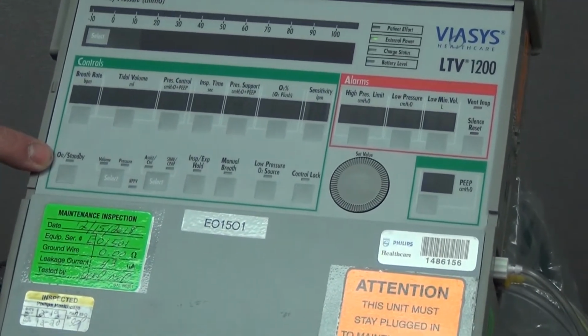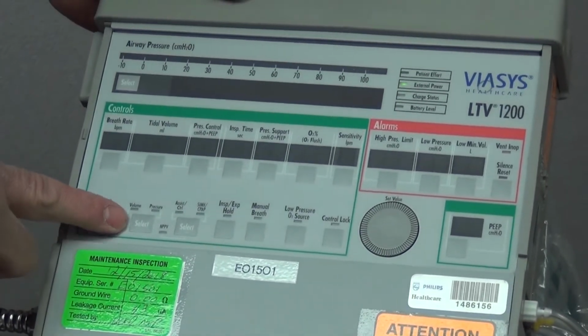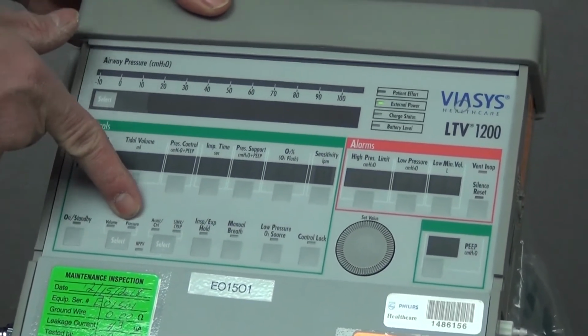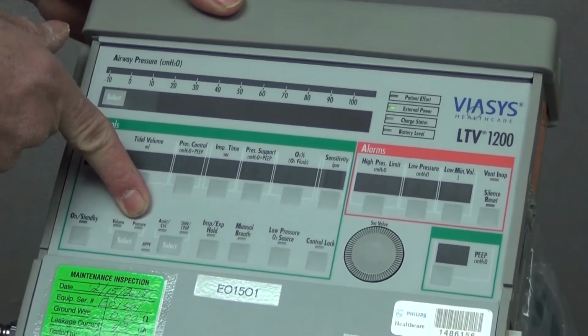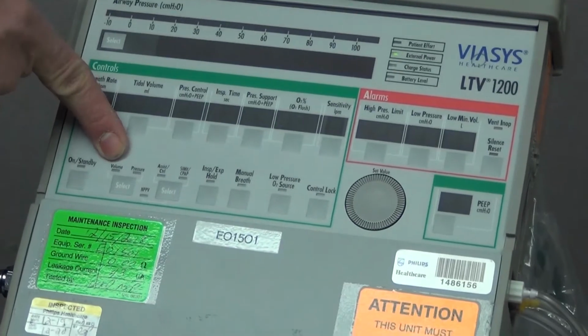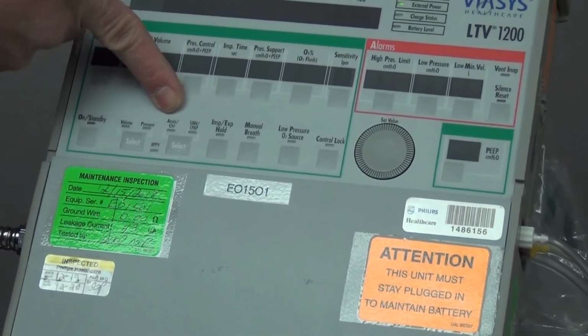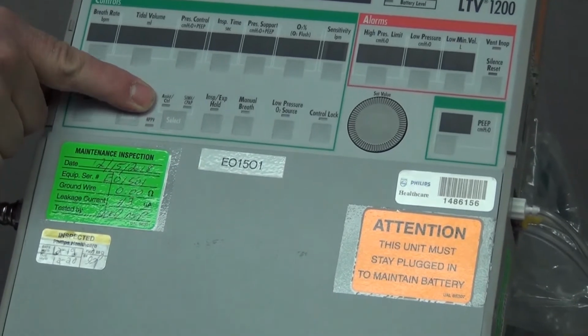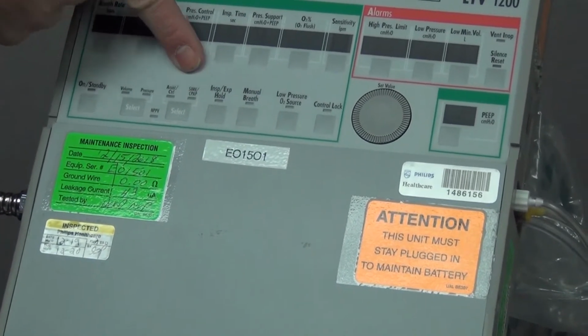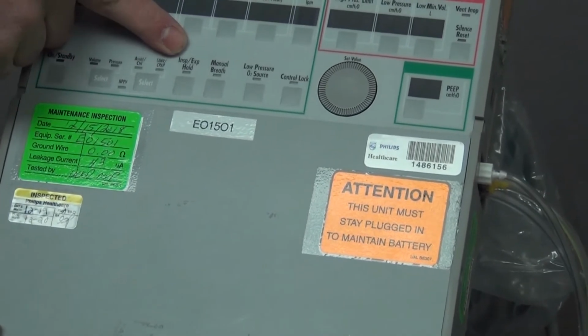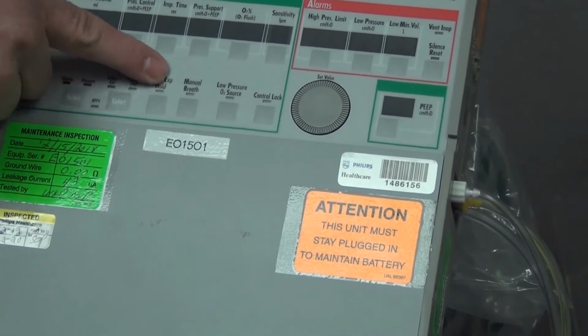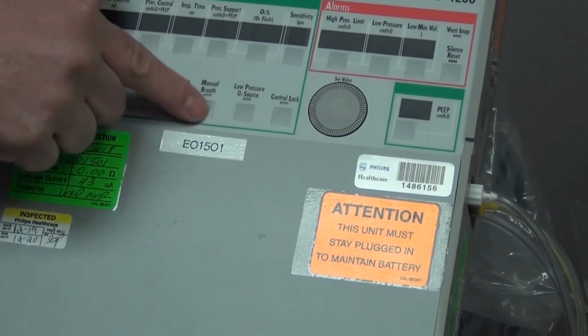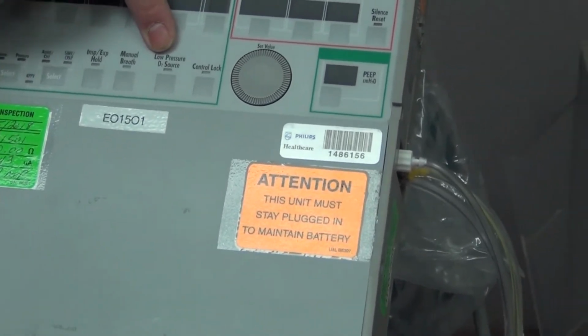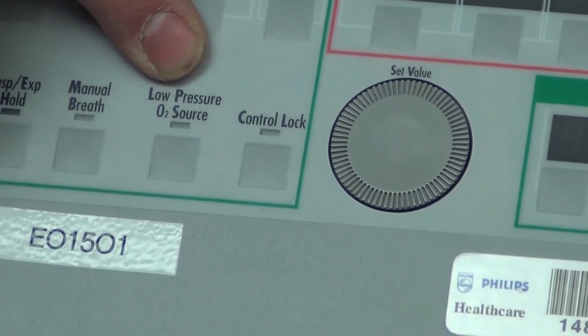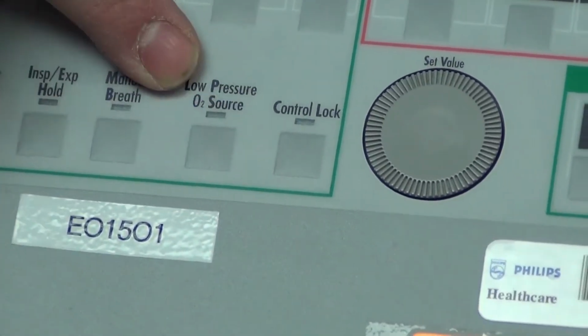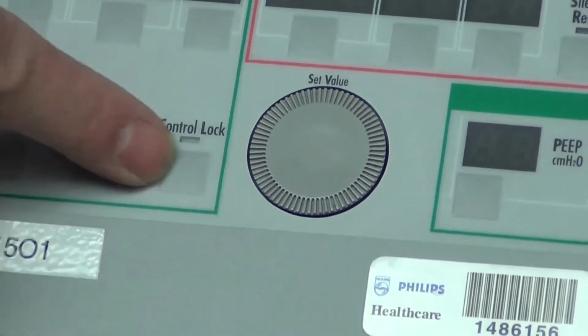First, here is your on standby. Next, you have your type of ventilation, either volume or pressure. In our first settings, we're going to use volume. This is the mode of ventilation. We're going to have assist control, and SIMV and CPAP are on this side. We're going to start with assist control. This one is an inspiratory hold and a manual breath. We will not use those. And this right here is just to show you if there's a low pressure. If I forget to plug in my oxygen line, this would light up. And then this is just a lock that we will not be using.